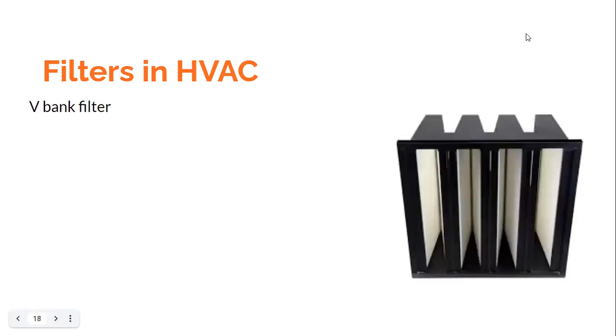The next type is the V-bank filter. This construction type houses a number of mini pleat filters in a V-shaped arrangement. Look at the diagram and you will see that this is a V-shaped arrangement for housing the filters. A number of mini pleat filters are housed in this V-type construction, which gives it the name V-bank filter. The advantage of this filter is that it has a higher handling capacity for a given delta P — that is, differential pressure rating.